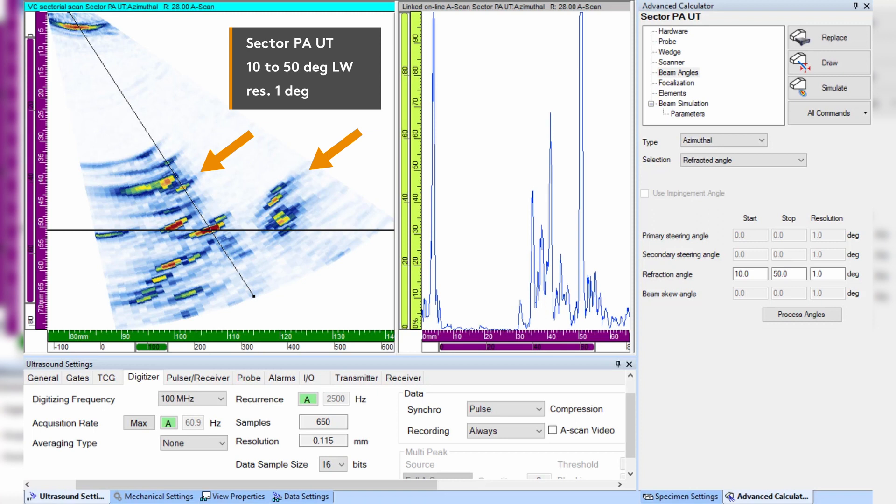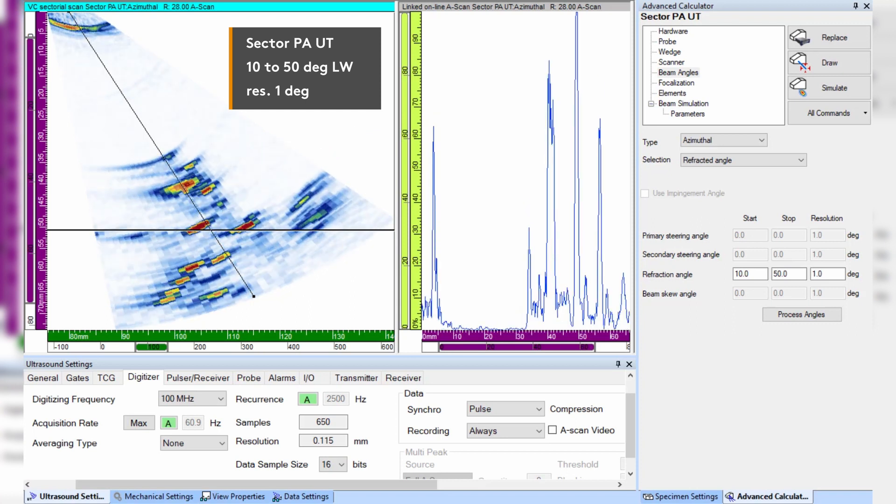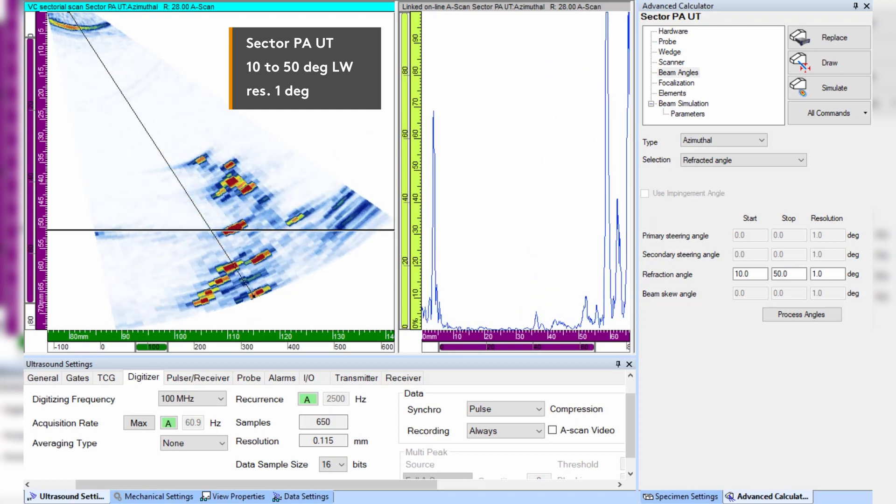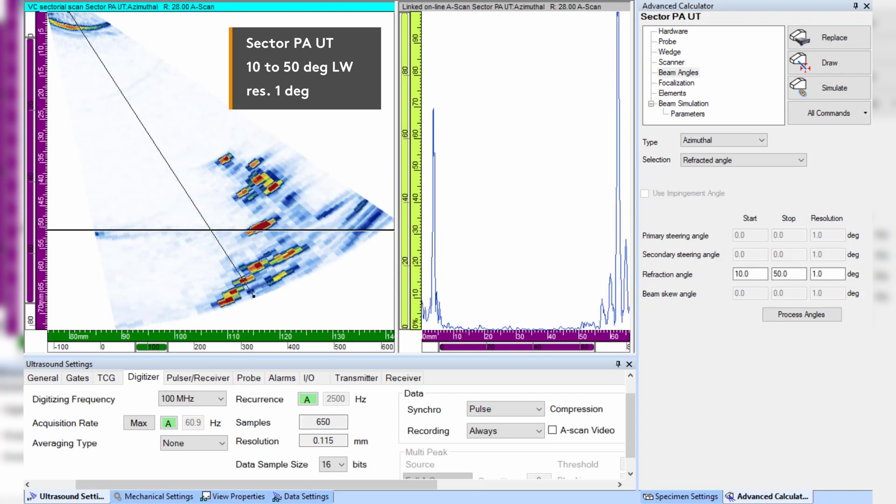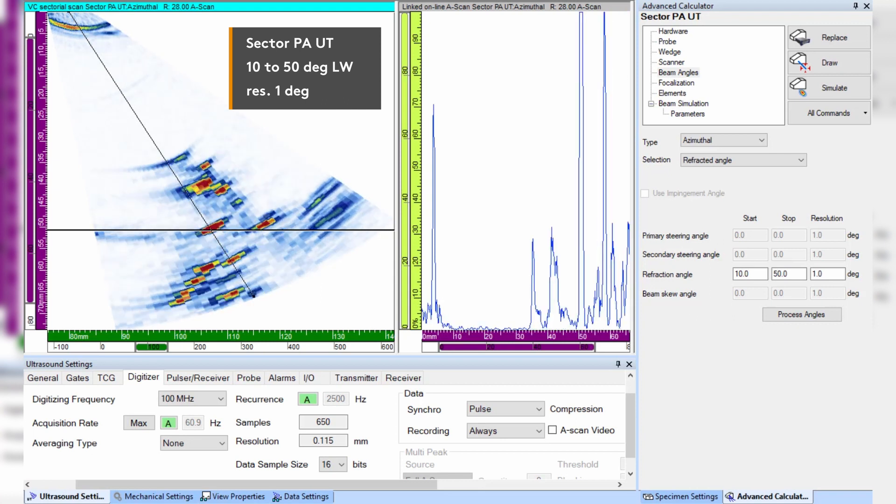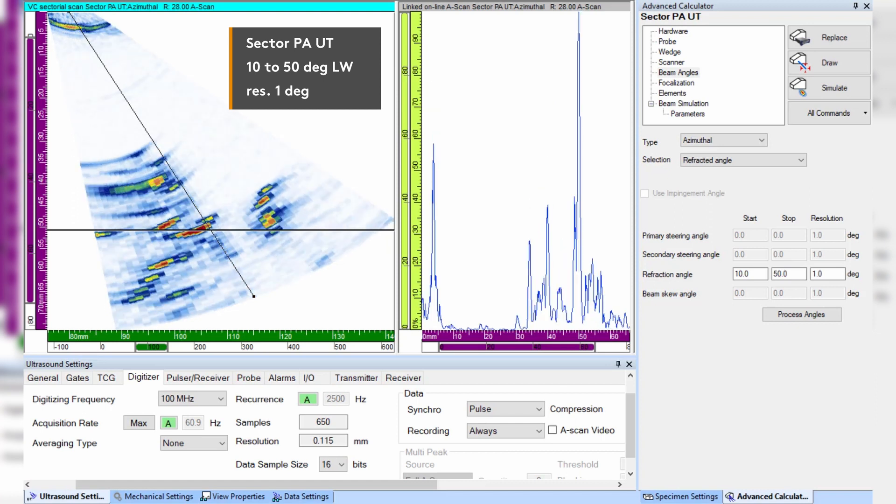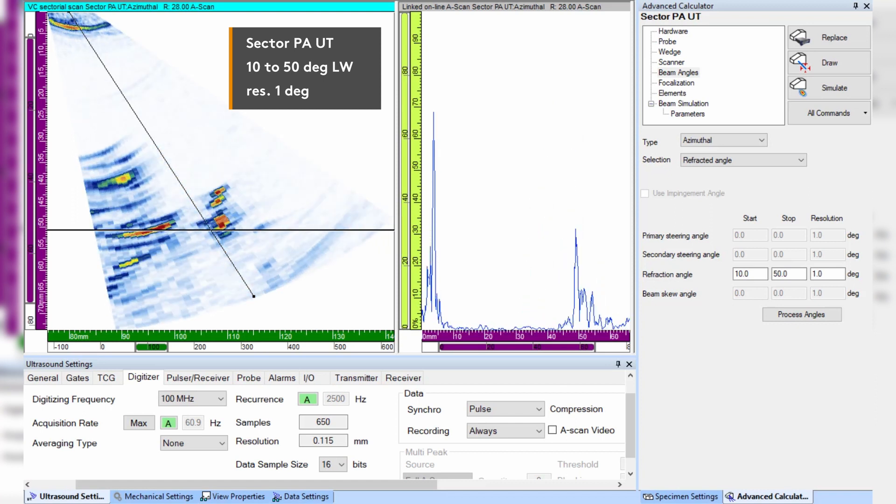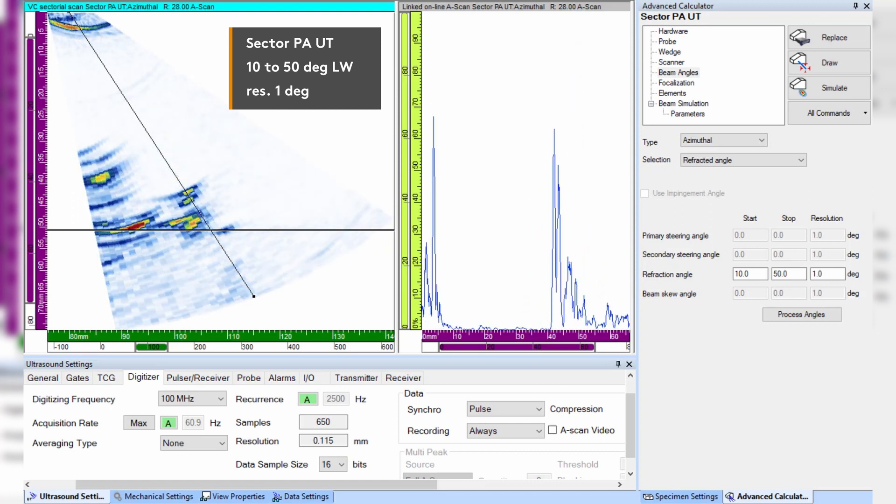We will demonstrate two advanced features of the Ultra Vision software: the new sectorial smoothing and the sectorial total focusing imaging. They can drastically improve the imaging of complex cracks while maintaining inspection productivity. Both cracks are well detected with phased array, but we would like better image resolution for flaw characterization.